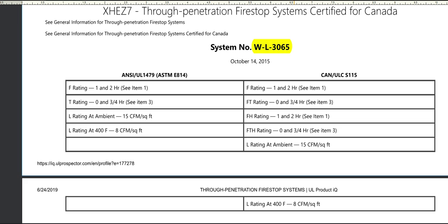The listing gives a date for when the system was last updated. Right at the top of the page it confirms the code requirements and the manufacturer test standards — the ASTM and UL standards found in code are listed right there, so I know I'm on the right track for a code-compliant listing. Then we see an F rating and a T rating, which I need to match up with my barrier to verify I'm in the right area. It's acceptable for one and two hour wall assemblies.